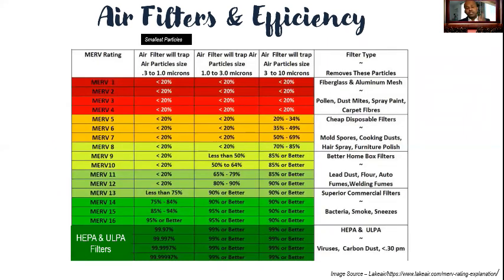Here is a table that I found, which is color coded, and I thought more user friendly. You can see the MERVs on the top, MERV 1 through 16, and then below that you will see HEPA and ULPA filters, for continuity. It shows you the range, and it also shows you the application. As I mentioned earlier, MERV ratings of 13 through 16 are higher quality filters. They require, of course, special blowers. They cannot be used in homes. They require commercial air conditioning systems.